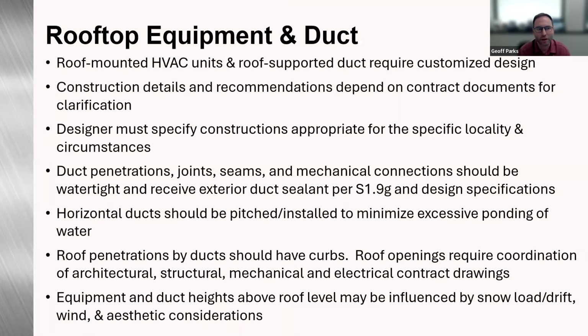Some rooftop equipment and ductwork. So roof-mounted ductwork and units and roof-supported duct do require a customized design. It's not the same thing as installing the ductwork within the building envelope. You have wind, rain, snow, ice, different loadings that need to be taken into consideration. Those construction details and recommendations would depend on the contract documents for clarification.